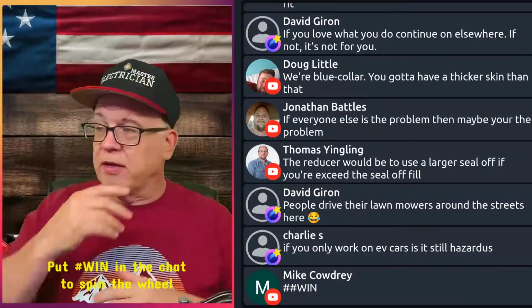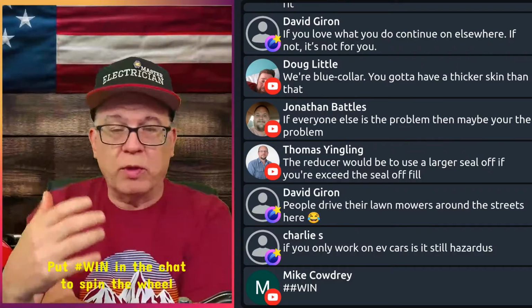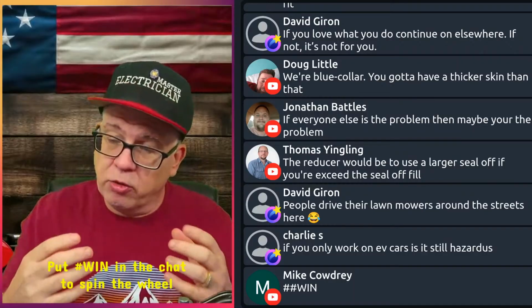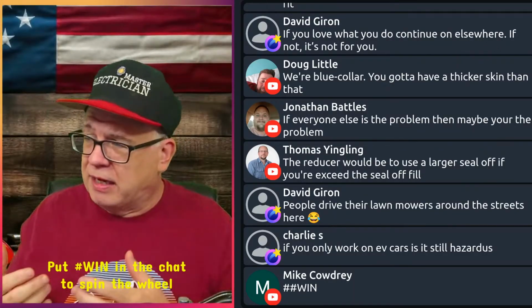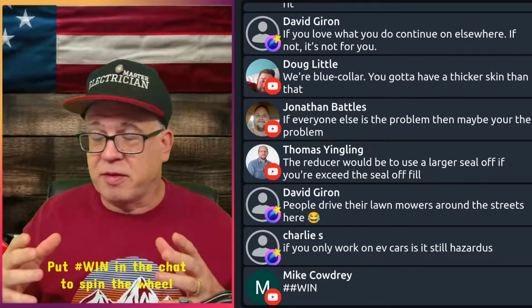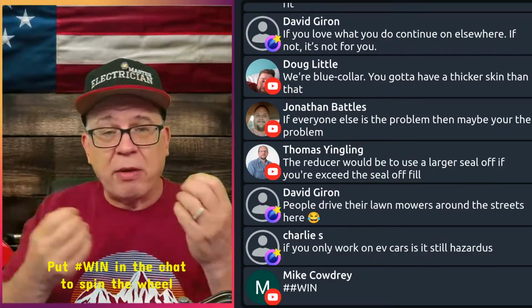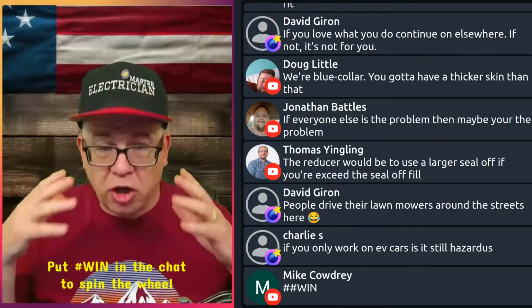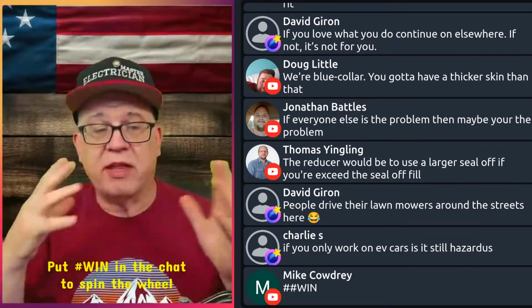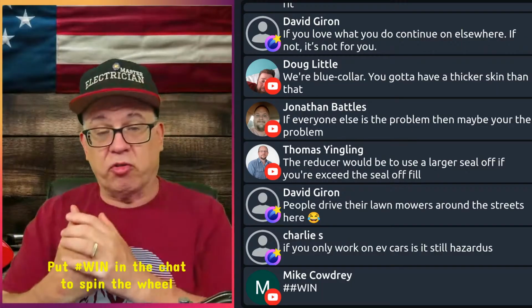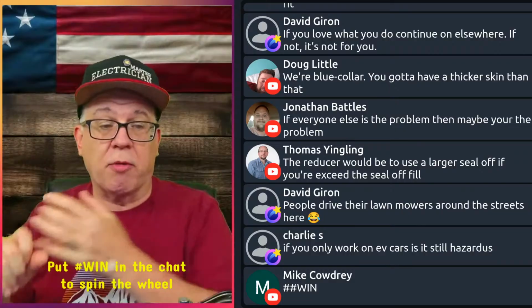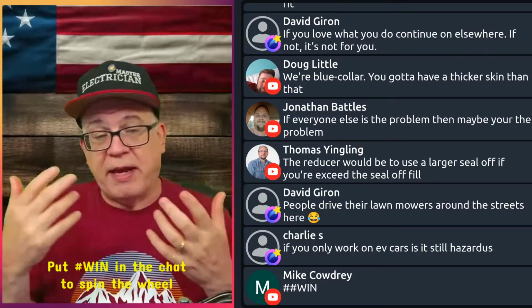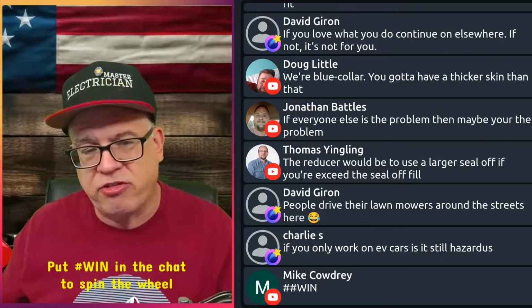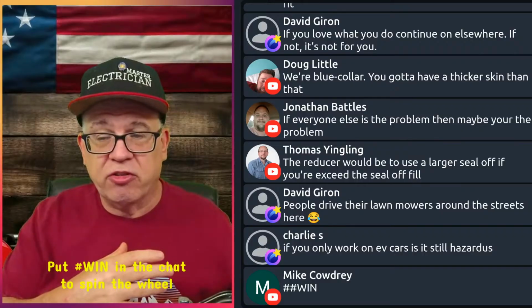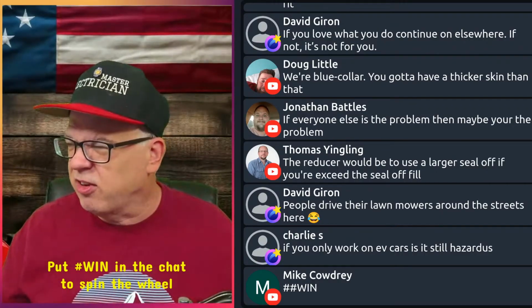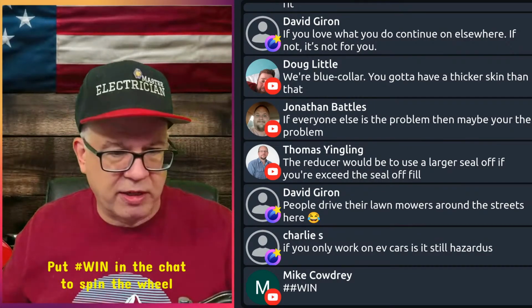We know that now we've got to go back and say, okay, what kind of gases are here, what kind of fuels do we have? So now we use 500 to make sure we know the type of location we're dealing with, the groups of different equipment that can be in these locations, depending on the gases we're dealing with. That's how they work together. So 500 is your base—you go there to establish the location and the division. Once you know that, you look and say, okay, I have a commercial garage. Again, it's important to know whether it's a major or minor repair, and what fuels, liquids, and vapors are involved. Then you can dig deeper into the locations. But you can't really get there unless you understand 500 to establish that—unless the engineer has already done it and is just telling you.